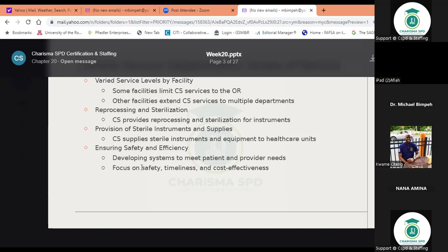When the Joint Commission comes and they interview you, you have to say it exactly the way the IFU is saying. The OR will understand that, yeah, that is our protocol. Sometimes when they're screaming, there was a time I had to provide a full lecture, putting time allocation on the decontamination. This tray is big. It could take about 25 minutes. The sonic takes about 10 minutes. The washer, about 15 or 20. I tell them, depending on the size.